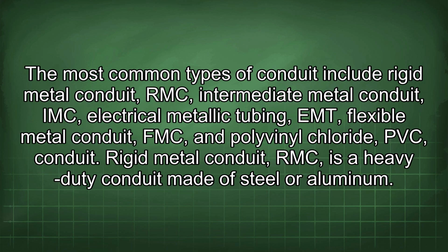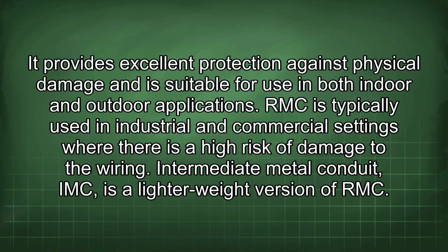The most common types of conduit include rigid metal conduit, RMC, intermediate metal conduit, IMC, electrical metallic tubing, EMT, flexible metal conduit, FMC, and polyvinyl chloride, PVC conduit. Rigid metal conduit, RMC, is a heavy-duty conduit made of steel or aluminum. It provides excellent protection against physical damage and is suitable for use in both indoor and outdoor applications.